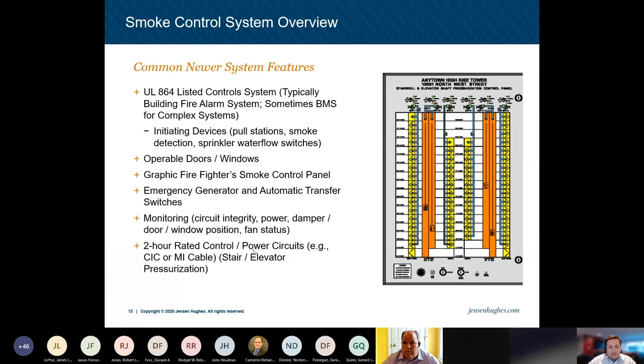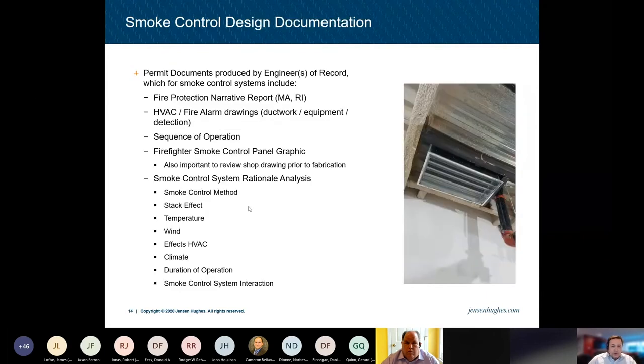Also, you'll have obviously VFDs, which are typically provided in newer systems and that allow for balancing and providing a safety factor in the fan as well. So smoke control design documentation, what to expect for what's produced by the engineer of record. You'll have the fire protection narrative, which is required in Massachusetts and Rhode Island. And it's a high-level overview of the codes, the design methodology, what's involved in that. It's not just smoke control, but it's all the fire protection systems in the building.